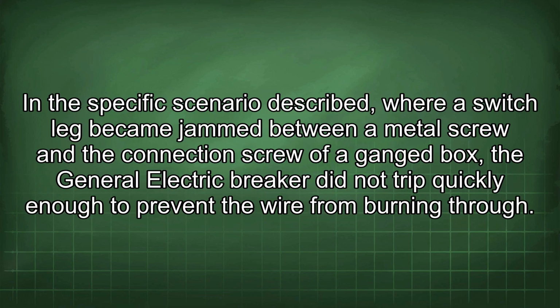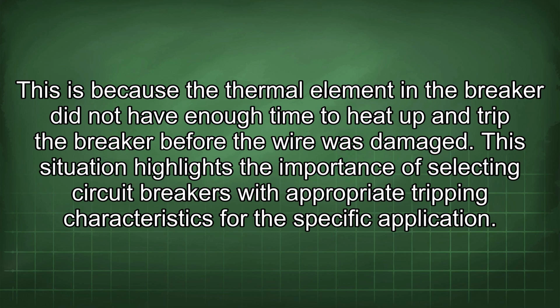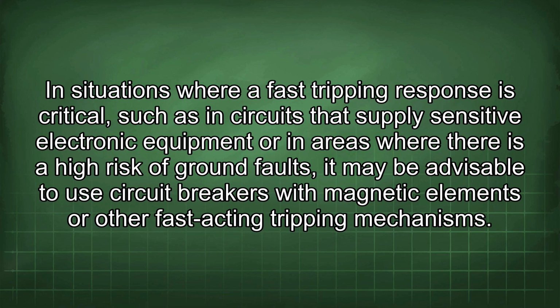In the specific scenario described, where a switch leg became jammed between a metal screw and the connection screw of a ganged box, the General Electric breaker did not trip quickly enough to prevent the wire from burning through. This is because the thermal element in the breaker did not have enough time to heat up and trip the breaker before the wire was damaged. This situation highlights the importance of selecting circuit breakers with appropriate tripping characteristics for the specific application. In situations where a fast tripping response is critical, such as in circuits that supply sensitive electronic equipment or in areas where there is a high risk of ground faults, it may be advisable to use circuit breakers with magnetic elements or other fast-acting tripping mechanisms.